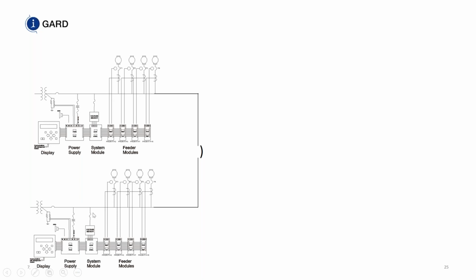So the way the system works is you have second fault protection. If you get a fault on one feeder on one phase and a different fault on a different feeder on a different phase, you have a line-to-ground to line-to-ground fault. The two feeder modules will communicate with each other, and the one that you program to be of a lower priority will trip first. This is why it's extremely ideal for data centers. Something has to trip when you have two faults on the system. But I-Gard gives the user control over what trips when you have a fault on the system.